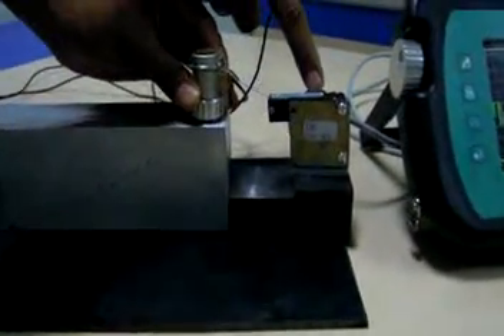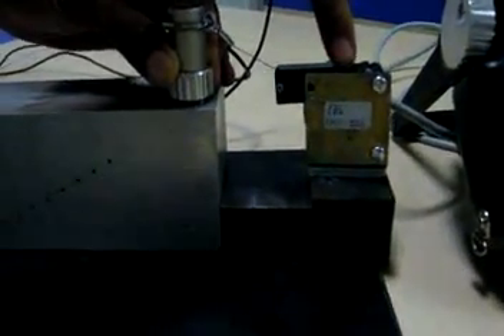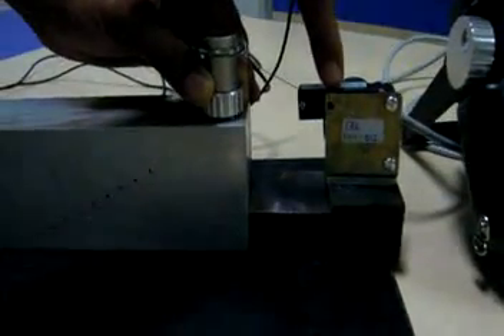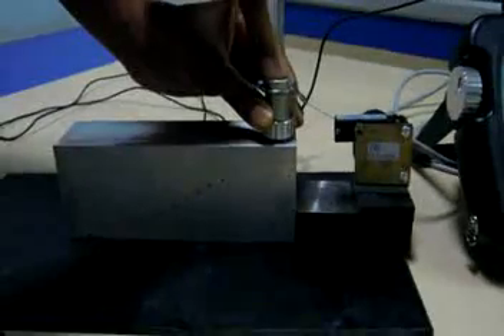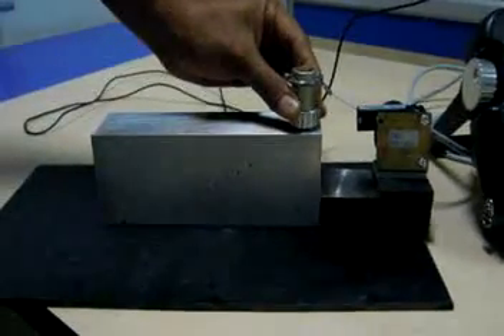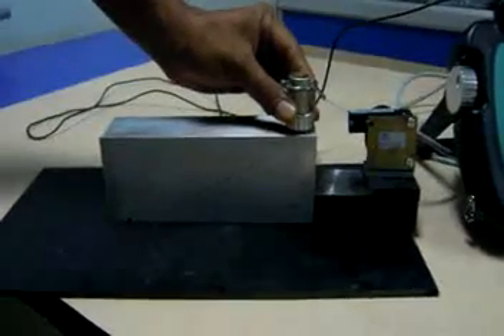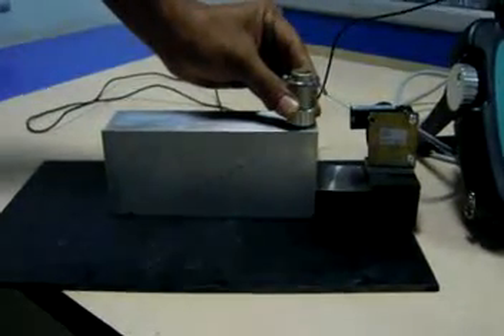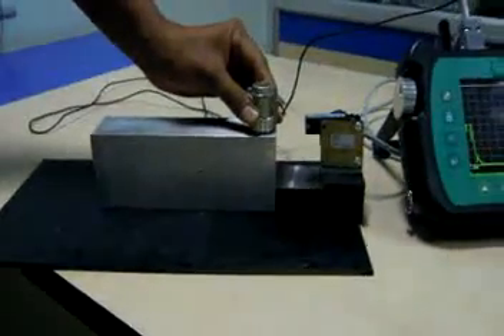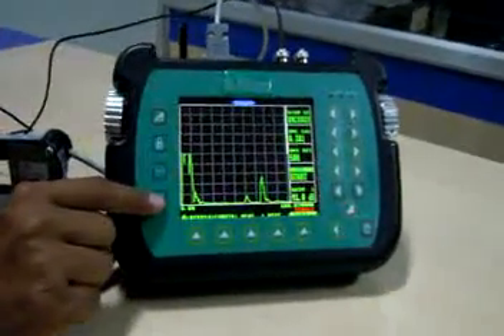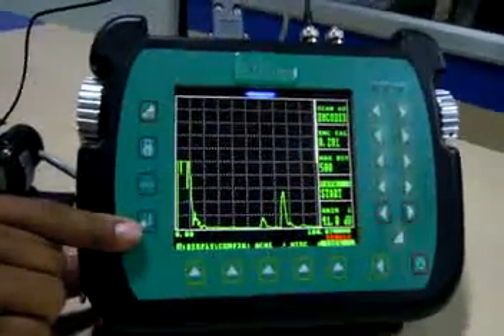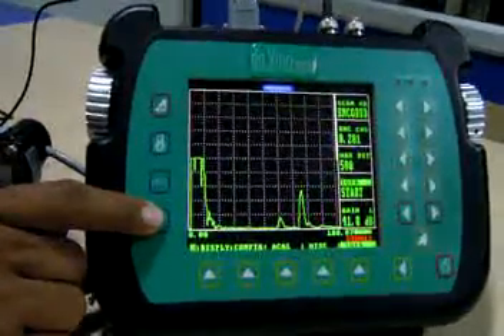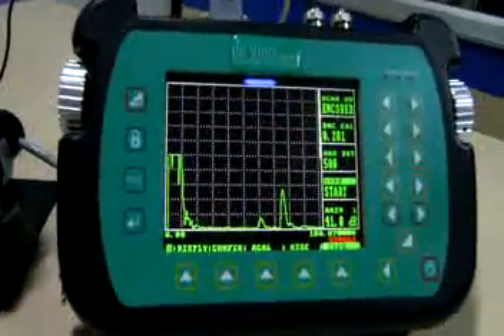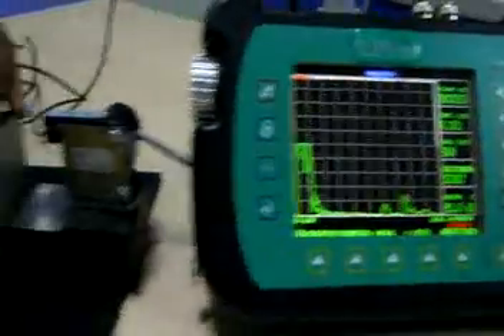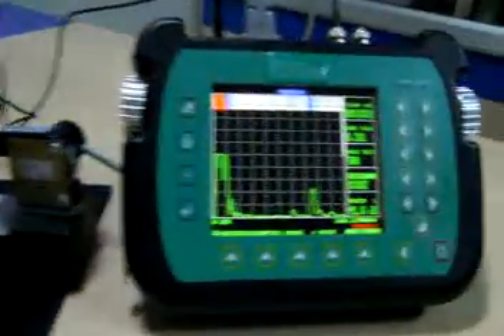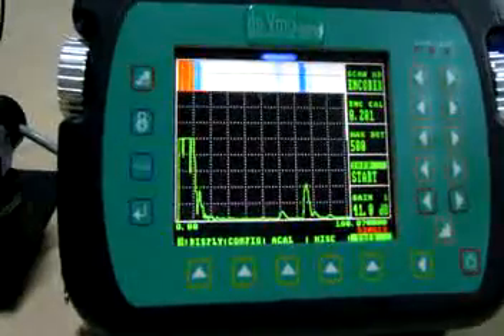And what you are seeing here is a string encoder that has been tied with the probe. So when the probe moves, the string gets pulled out and the probe position can be known. Its data is entered inside the machine input. So now, this is the machine, and now we are pressing the key to enter, and you will see that as soon as the probe starts moving, this B-scan image is being generated.